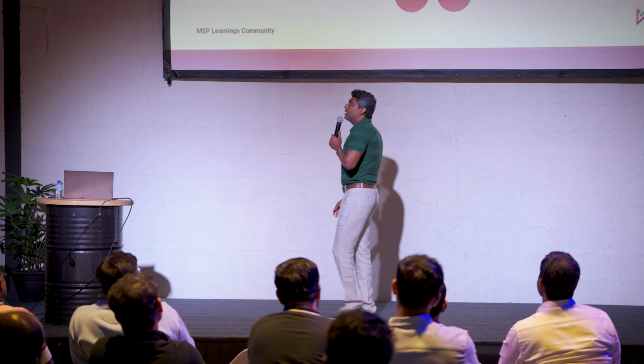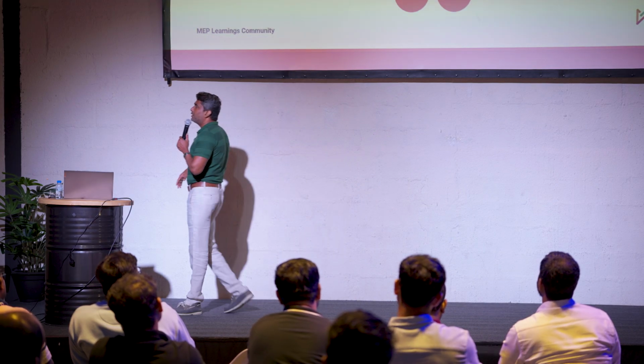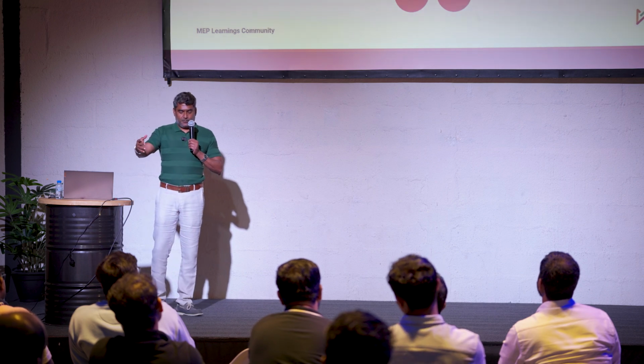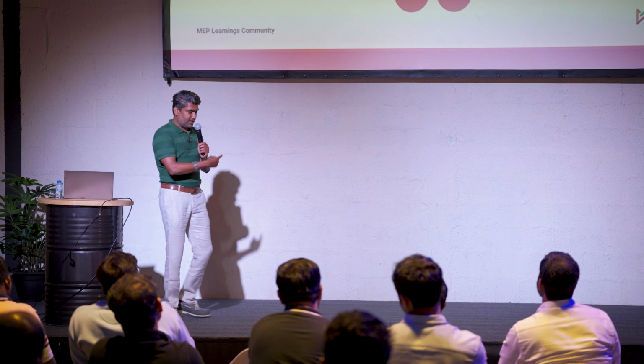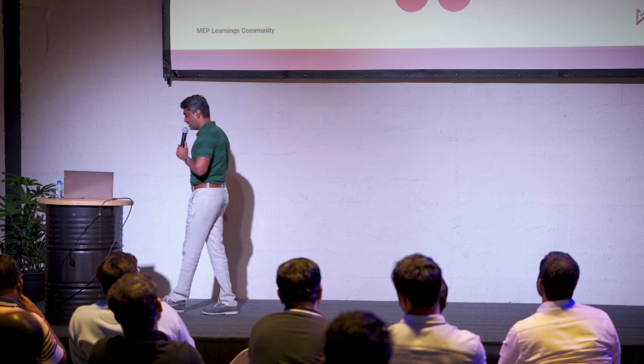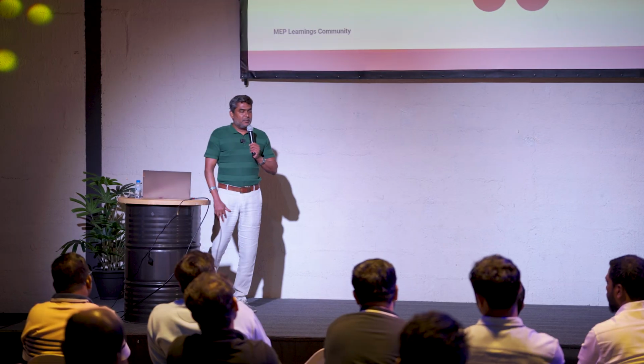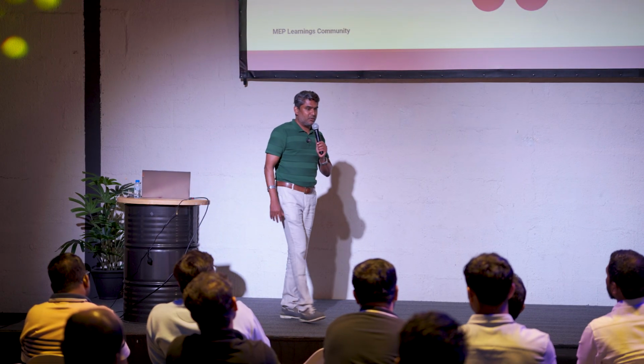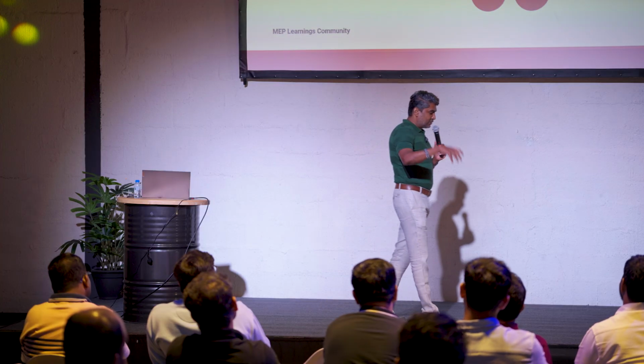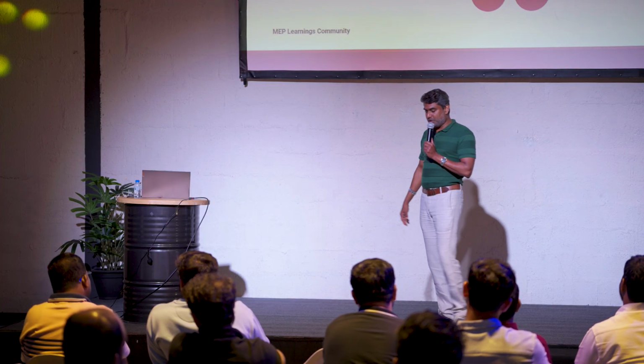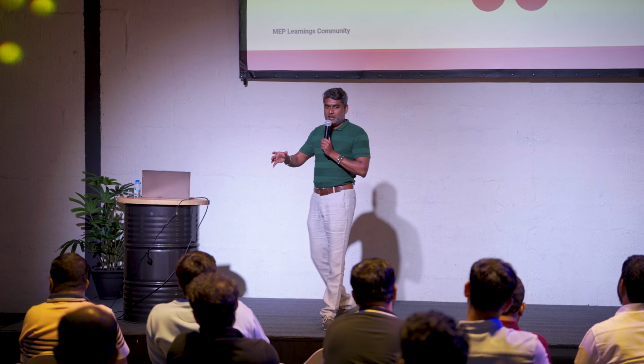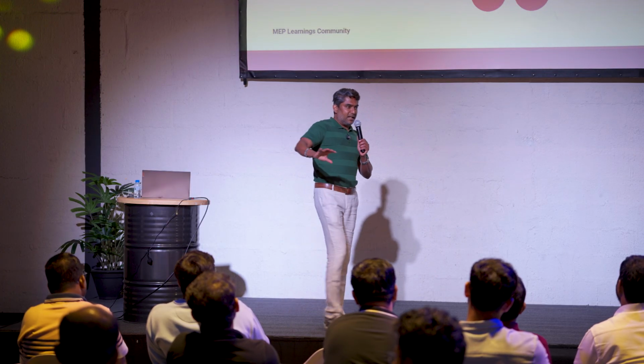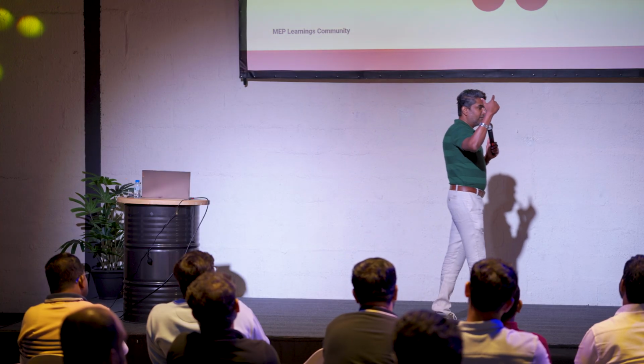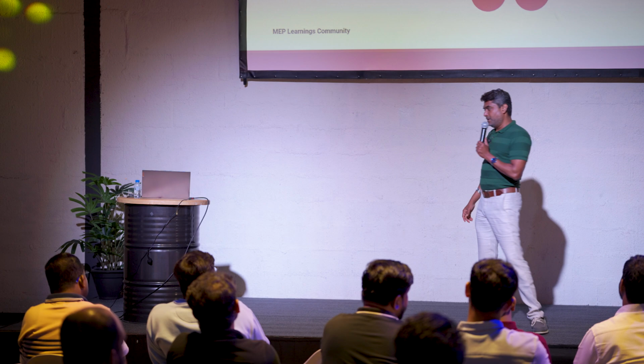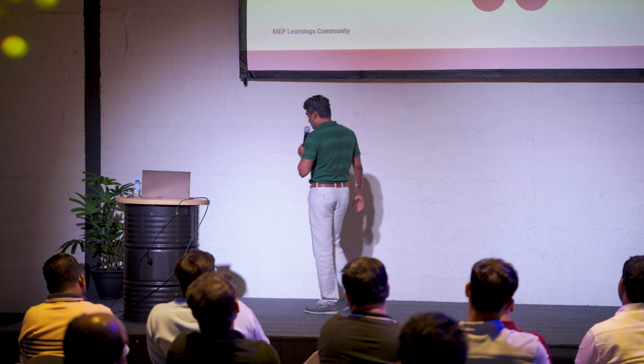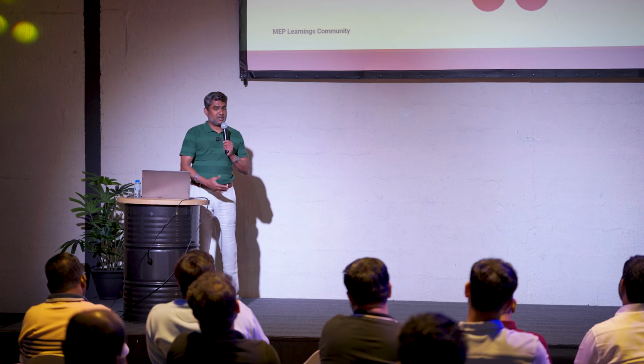So, don't you think it's about the safe evacuation of people? The next point, as the gentleman earlier—sorry, I forgot his name, Safwan—mentioned, is about fire rated ducts and fire propagation. The fire should not propagate, so whenever ducts cross floors, or from the branching which comes to a floor from the riser, you will have a damper. If that damper is open, the fire is going to find a way through it, so it has to be closed. The purpose of the fire alarm system is to safely evacuate people, and this also serves that same purpose.